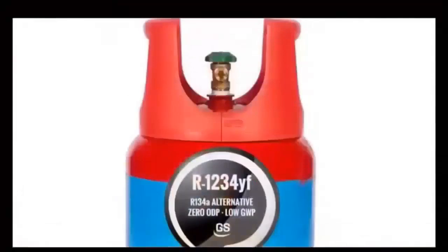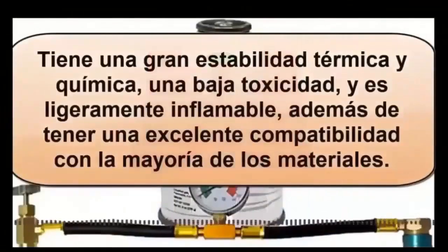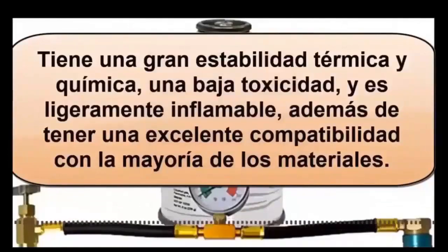Like all HFO refrigerants, R1234YF is non-ozone depleting and has a low GWP of only 4. R1234YF refrigerant has high thermal and chemical stability, low toxicity and is slightly flammable, as well as excellent compatibility with most materials.